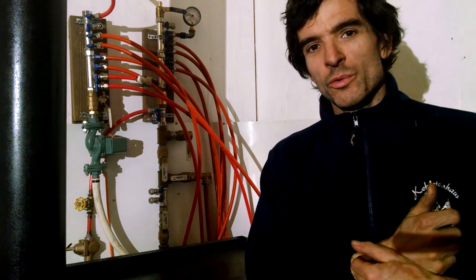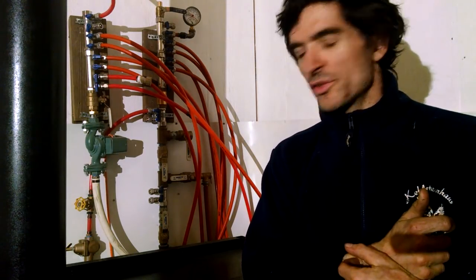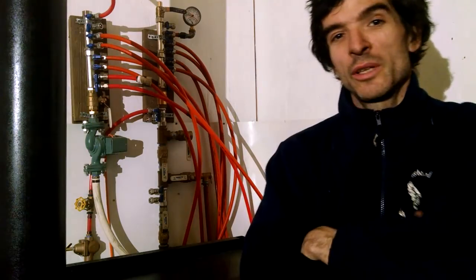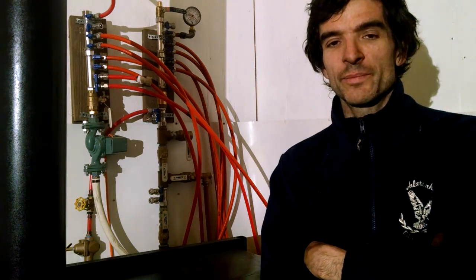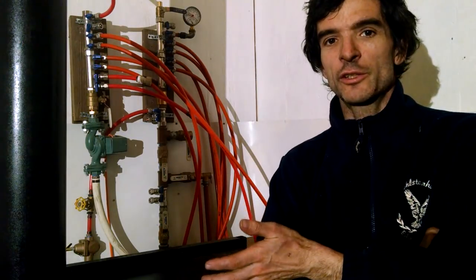Major lesson though: we noticed that within about 3 hours from the time the stove goes out, the house gets pretty cold. In the last house, we put in about 4 cubic yards, about 10,000 pounds or so, of sand under the floor, and that can retain the heat much longer, for about a day or so. So that's a major learning, to keep the thermal mass inside the floor. Put sand right with the hydronic tubing, which we didn't do this time around. That'll be a great addition for next time.